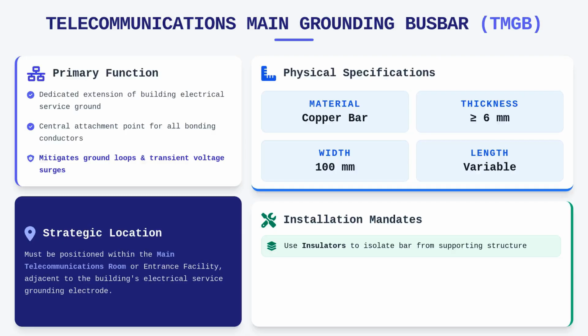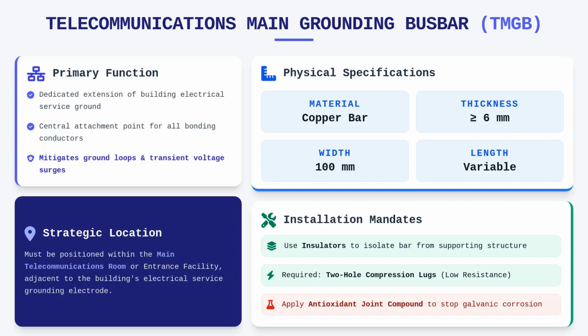Every connection to the TMGB should employ two-hole compression lugs, which provide superior mechanical stability and lower contact resistance compared to single-hole solutions. Before attaching the lugs, it is imperative to apply an antioxidant joint compound to the contact surfaces to prevent oxidation and ensure the longevity of the electrical bond. This attention to detail prevents galvanic corrosion, which is a silent killer of grounding integrity in high humidity environments.